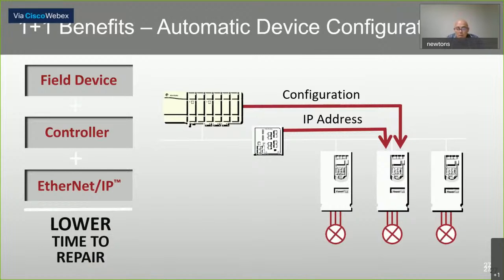And then once the logic processor identifies that IP address, it will automatically flash and then push down the configuration parameters for that drive. So in this case, it certainly would lower time to repair and possibly eliminate the need of a technical person to do that, maybe a mechanic or electrician, someone just simply to replace the hardware, and then the software is replaced automatically.